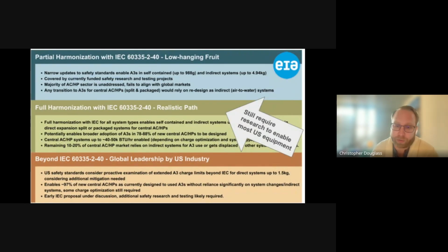Now, that second green box would enable a much larger portion of the market. That would be if we harmonize with IEC fully in terms of their charge sizes, which would be almost 80 to 90% of the US market. However, larger capacity systems above 50,000 BTUs would still remain outside of R290 feasibility in a direct system, so those would need indirect or other alternatives. Now, that third box could open up a pathway that gets nearly all U.S. equipment able to transition to R290 or other hydrocarbons. This would, of course, require a deep examination of safety and feasibility of allowing greater charge sizes for direct systems between 1.5 and 3 kilograms.